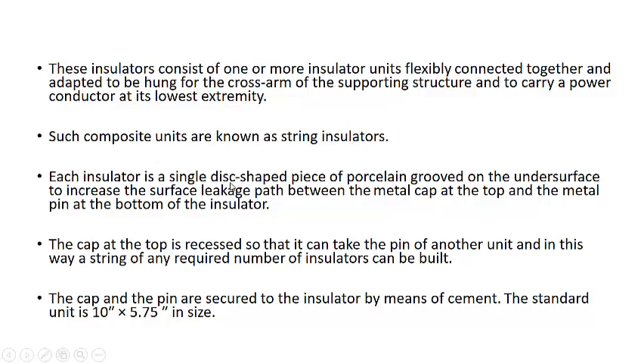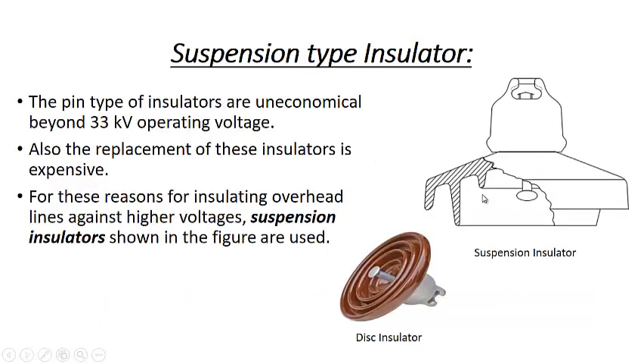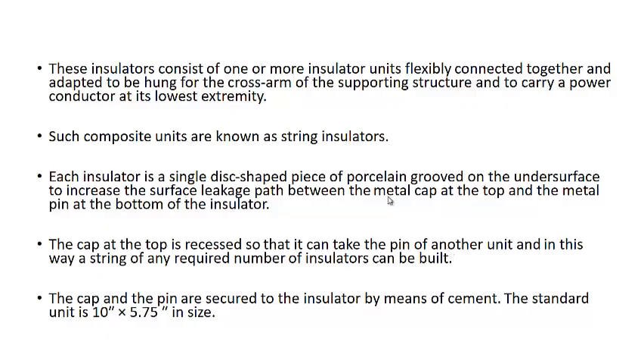Each insulator is a single disc-shaped piece of porcelain, grooved on the undersurface to increase the surface leakage path between the metal cap at the top and the metal pin at the bottom of the insulator. You can see that these are made like this so as to increase the leakage path, which is known as creepage distance, so that leakage resistance is increased and leakage current is decreased. The cap at the top is recessed so that it can take the pin of another unit, and in this way a string of any required number of insulators can be built.